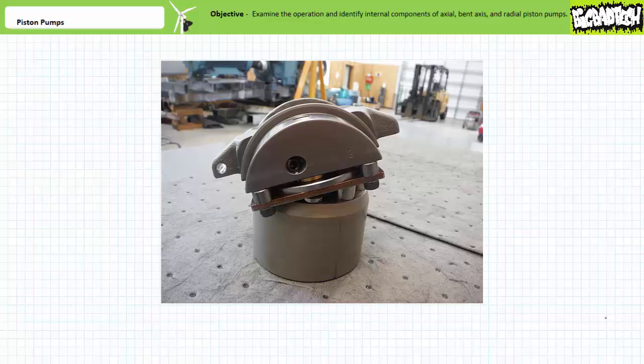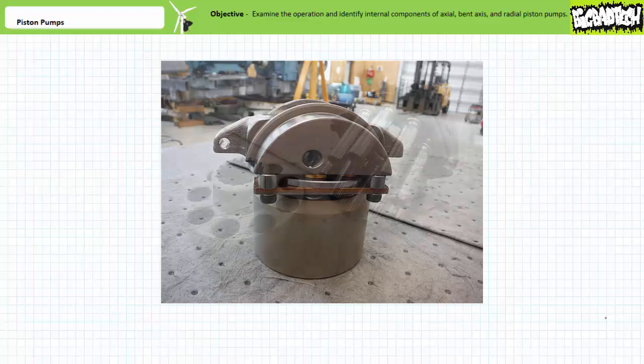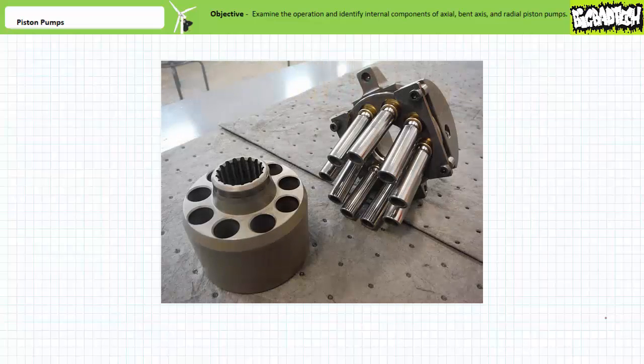When the swashplate is held at an angle, a volume differential exists inside the piston block as the driveshaft is rotated 360 degrees. When the swashplate angle is at a maximum, flow rate is at a maximum. When the swashplate is held flat, no volume differential exists and flow rate is at a minimum. We can remove the pistons from the piston block. Note the ball and socket assembly on the pistons allow them to swivel with respect to the swashplate and still reciprocate axially inside the piston block.